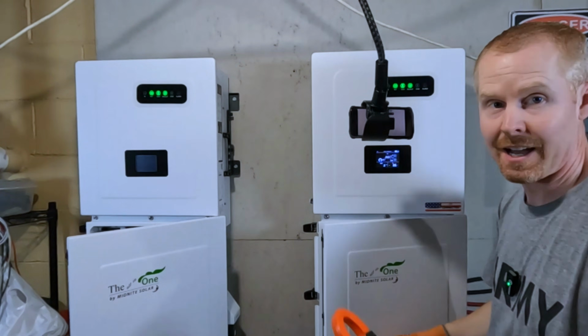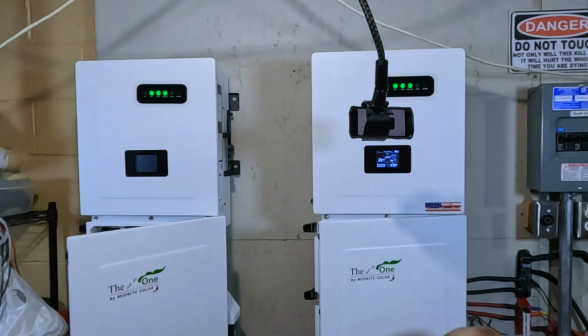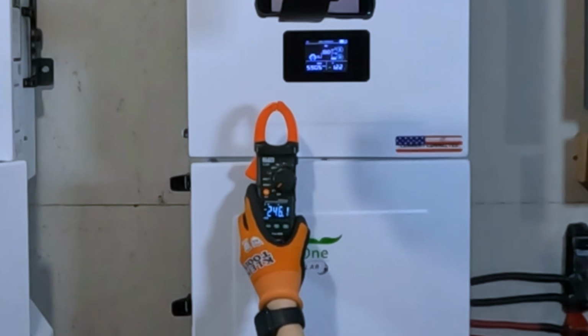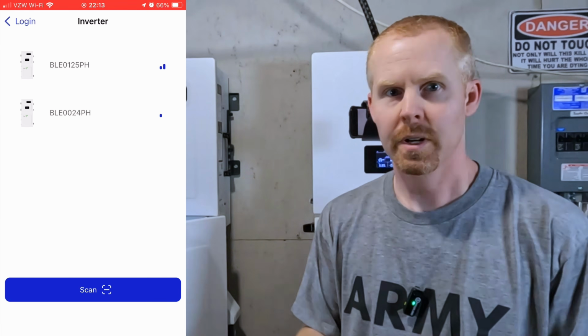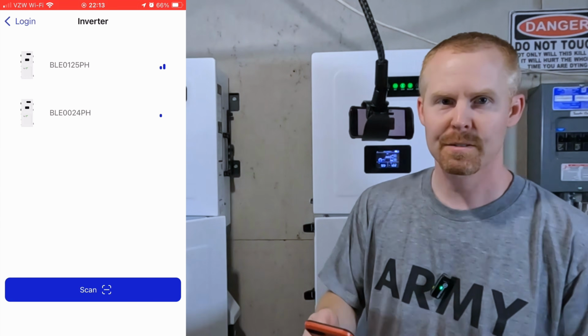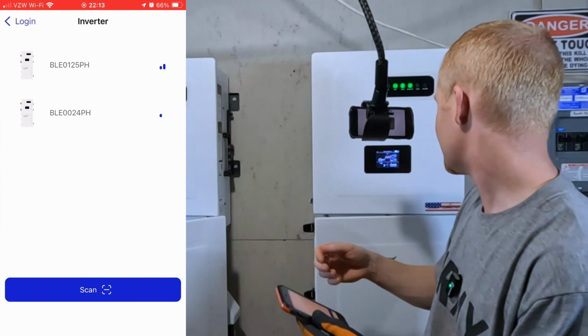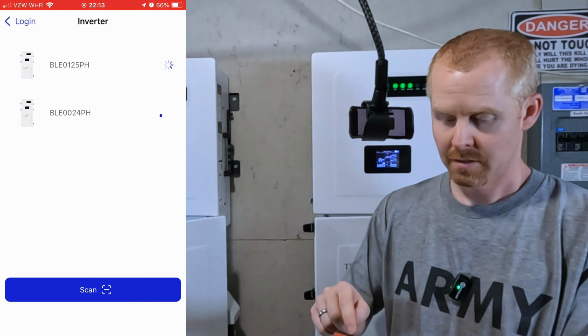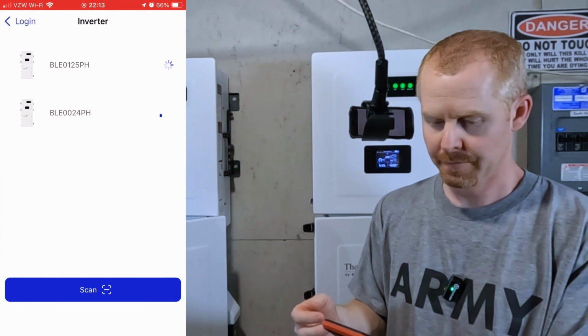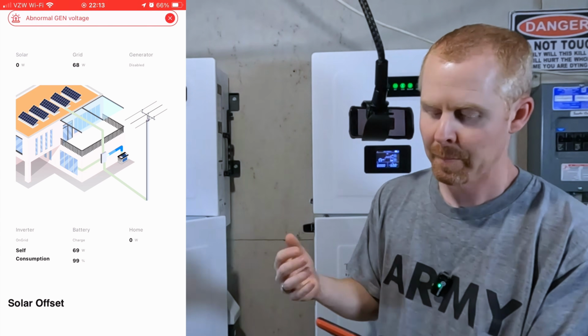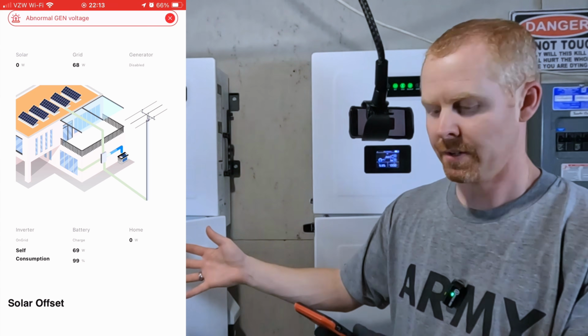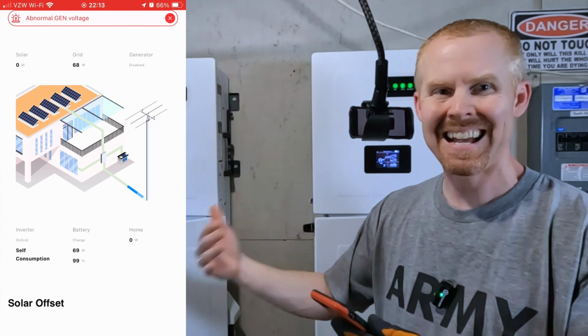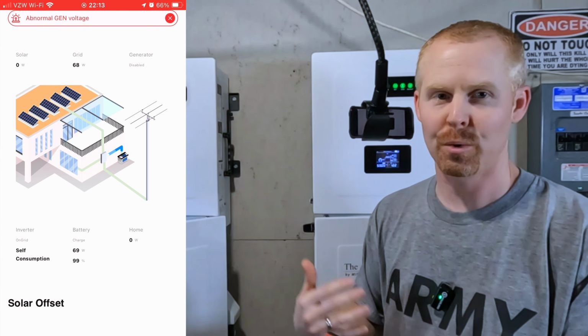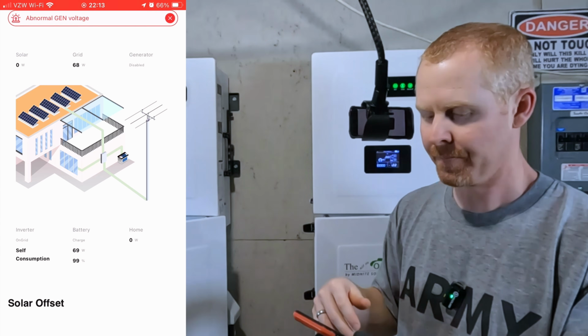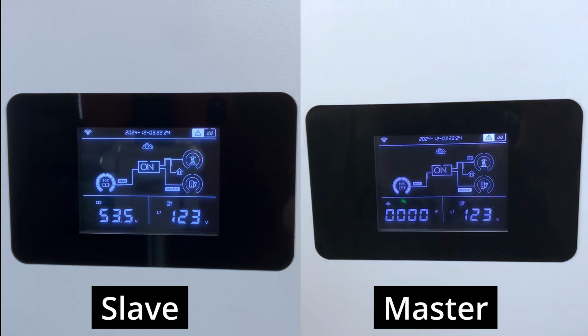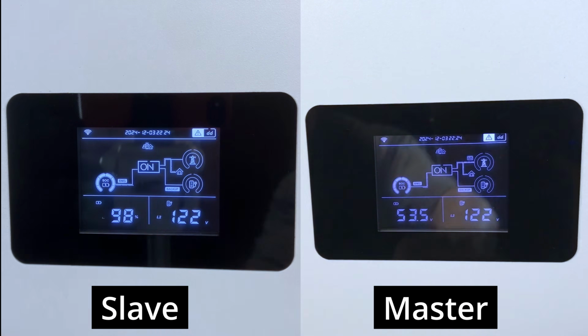So now if I check the output down at the PDB, 246.1. I do want to look and see—the camera's going to smack me in the head—what the DD error is. So let's go into the master inverter: abnormal gen voltage. I had configured the generator input and it's not detecting any generator input, and that's why it's throwing the DD error.